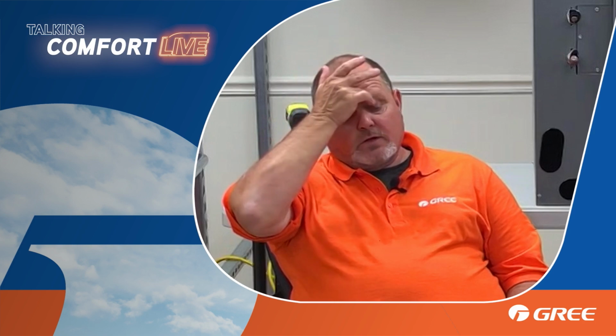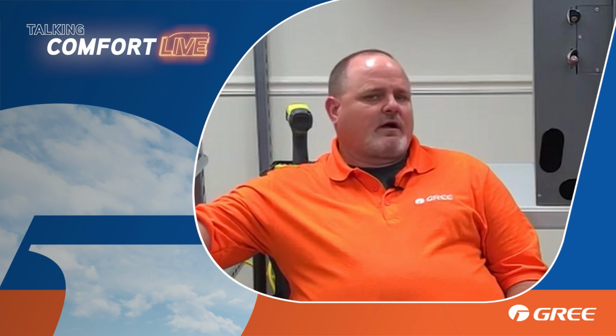Now, one thing I will point out that I like to talk about is that some of it has to do with efficiency too. If you're talking multi-zone units, and let's say you were putting a multi-EO in and you were using Sapphire heads, typically the Sapphire head is going to have a larger line set than if I use a Livo head, because the Livo heads don't have as high efficiency. Right. So sometimes you can fix your line set being too small by going to a different indoor unit. Yeah. So it's not always just about oil return and discharge, but it could also be efficiency. Good point. So there's more than one thing that signifies line set size.